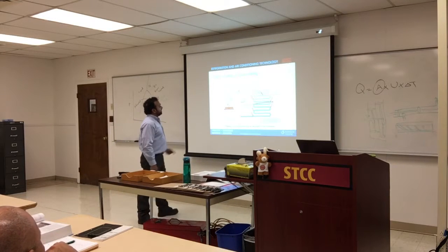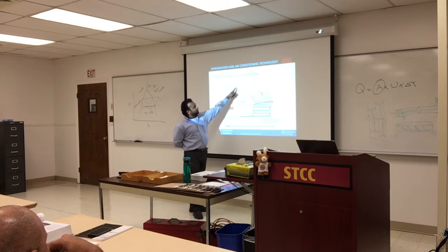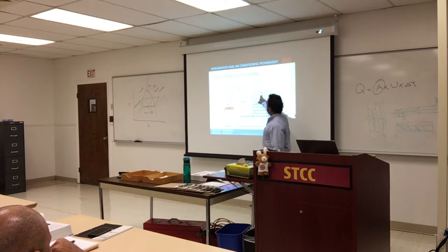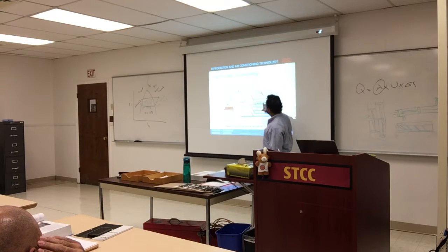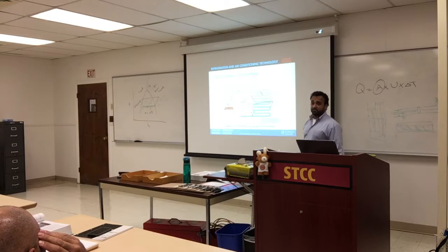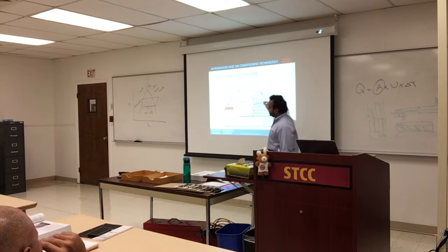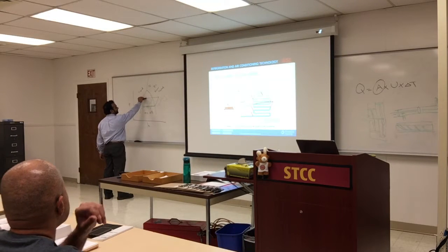So let's look at it a little bit. We have suction line from the evaporator, right? And we said this temperature is really high, superheated, completely vapor coming in. The pressure is 278, temperature is 200. It goes all the way to the condenser. As it goes around, the temperature starts dropping, because again, we're running air coming at 95. This is at 125, so we have 30 degrees temperature difference. So eventually it's going to lose heat. The pressure was constant, but we lost some heat. So what happened? It went back towards the left.